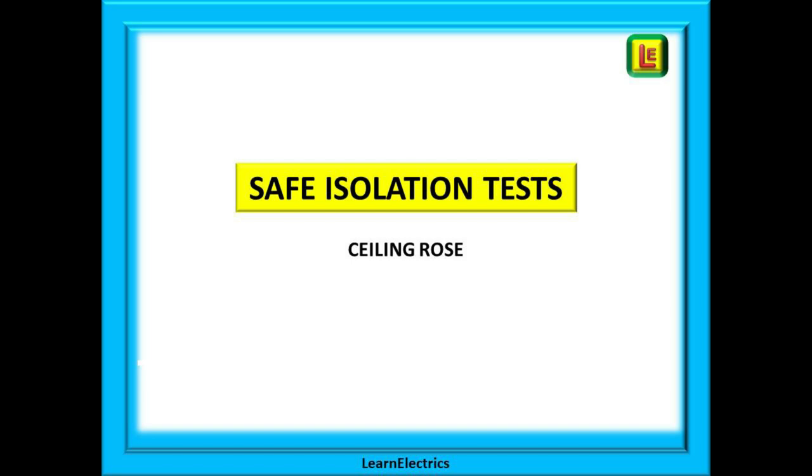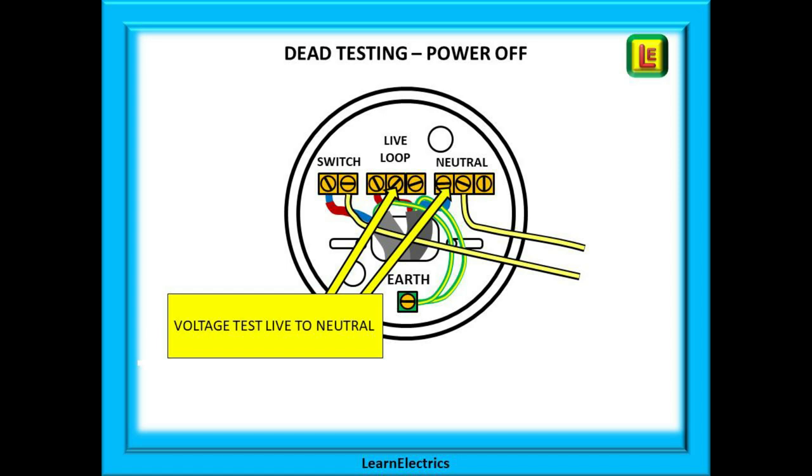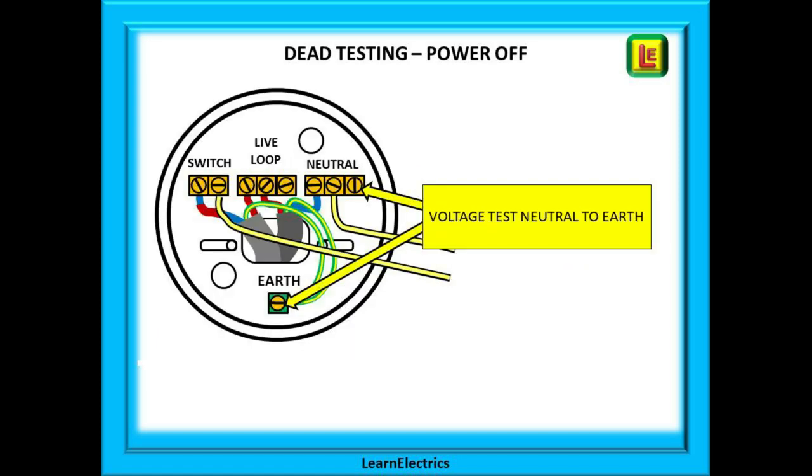And how would we check for safe isolation at a ceiling rose? Very simply, it is no different to the other single phase tests. After locking off and isolating, check with your voltage indicator between live and earth, then between live and neutral, and finally between neutral to earth. If they all read zero volts, that has proved safe isolation.